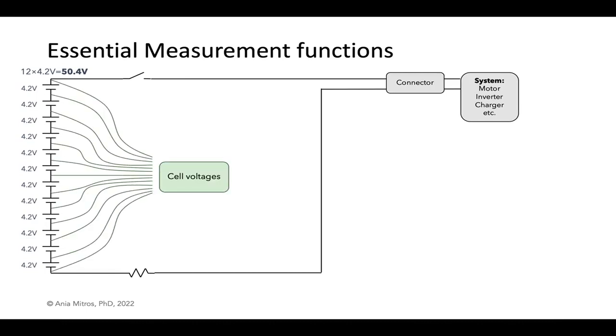We for sure must monitor the cell voltages, and we need to measure all of them. If any cell becomes overvoltaged, it can be damaged, and many lithium chemistries can go exothermic, which is a fancy word that should have you thinking about smoke and fire. So, no cell, not even one, should be charged beyond the maximum voltage specified by the cell manufacturer.